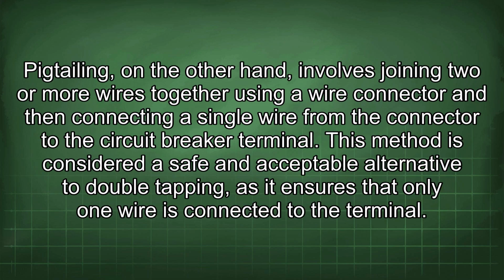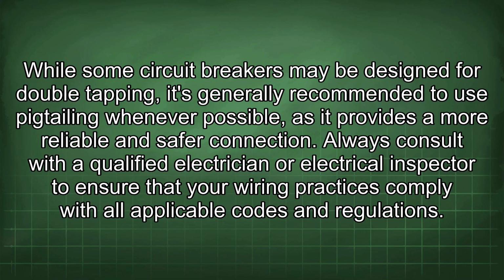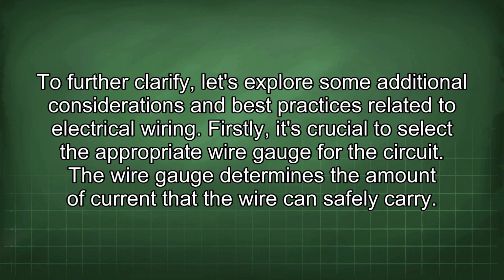Pigtailing, on the other hand, involves joining two or more wires together using a wire connector and then connecting a single wire from the connector to the circuit breaker terminal. This method is considered a safe and acceptable alternative to double tapping, as it ensures that only one wire is connected to the terminal. While some circuit breakers may be designed for double tapping, it's generally recommended to use pigtailing whenever possible, as it provides a more reliable and safer connection. Always consult with a qualified electrician or electrical inspector to ensure that your wiring practices comply with all applicable codes and regulations. To further clarify, let's explore some additional considerations and best practices related to electrical wiring.